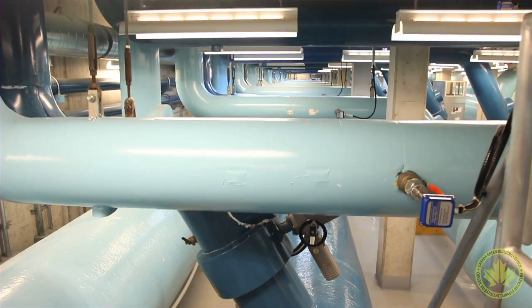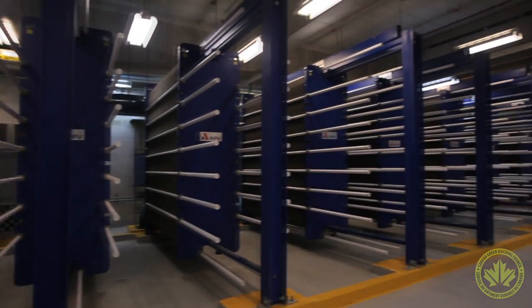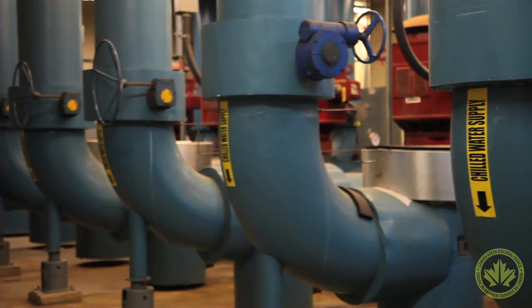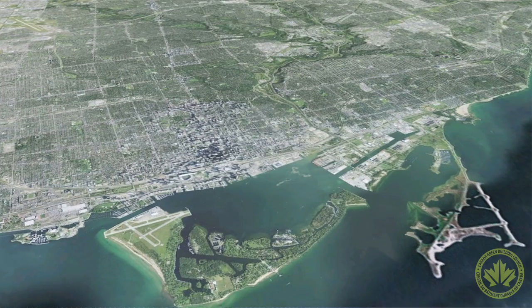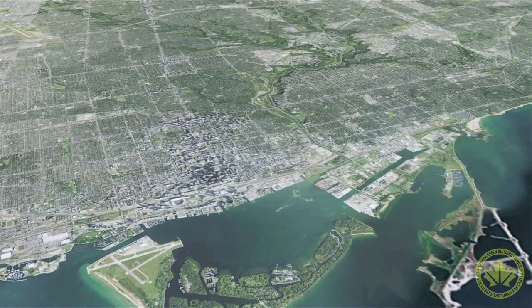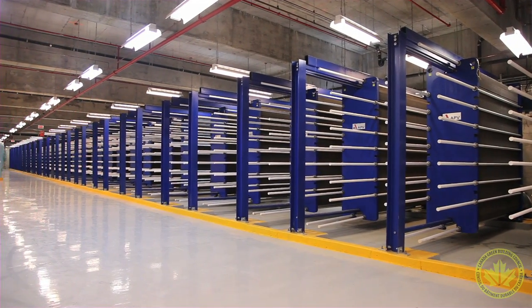We're here at Edwards. We take water from the bottom of Lake Ontario to many of Toronto's largest owners. Quite simply, we take water from the bottom of Lake Ontario — nice cold, 4 degrees Celsius water. That water is treated as drinking water by Toronto Water and then pumped through a large set of heat exchangers here in this facility, transferring cooling energy otherwise performed by large chillers or air conditioners at our customer sites.